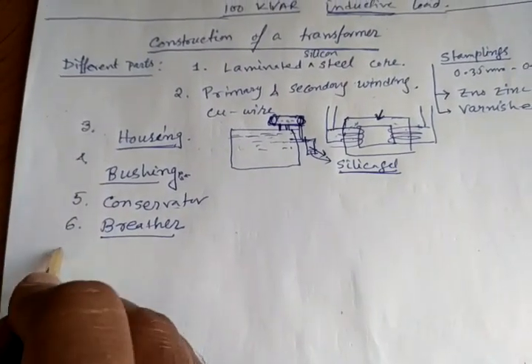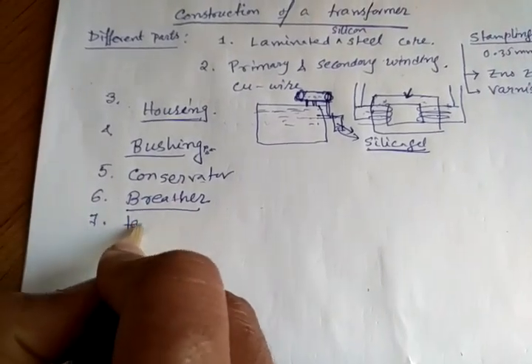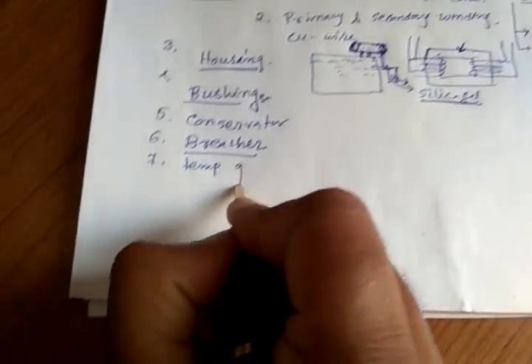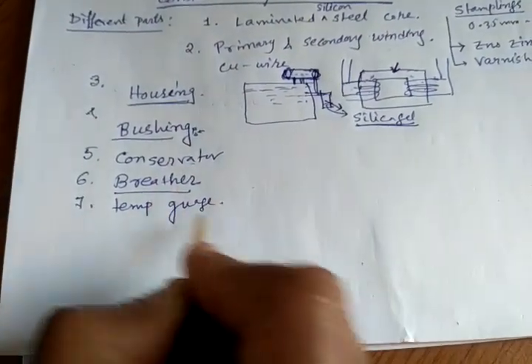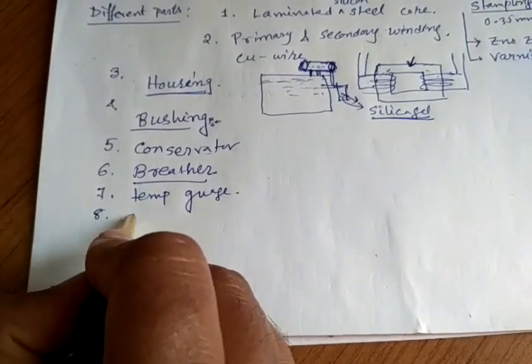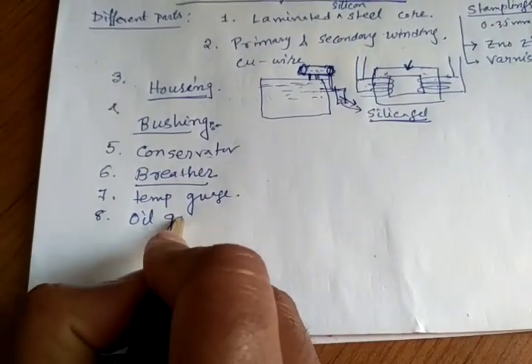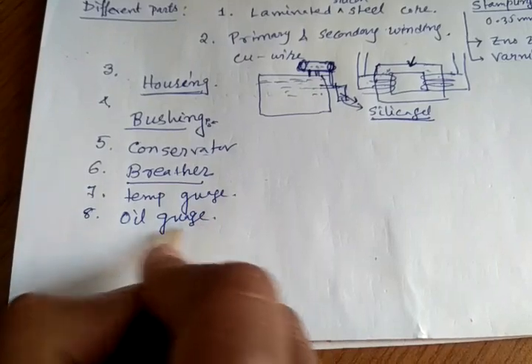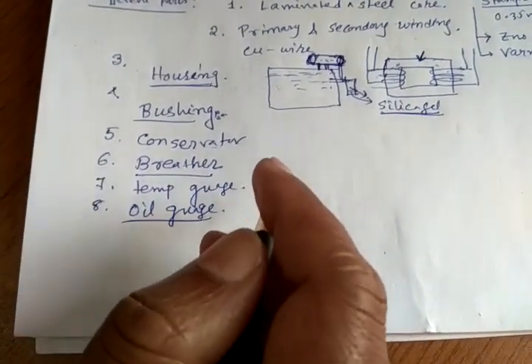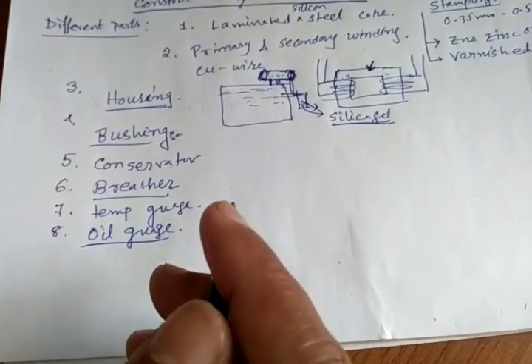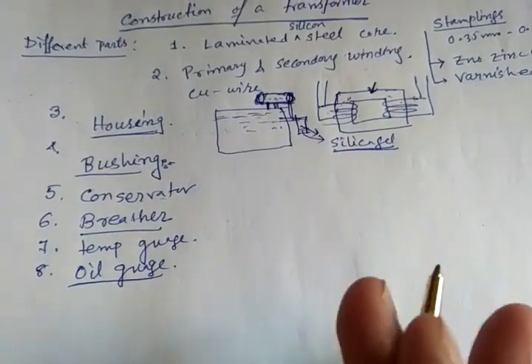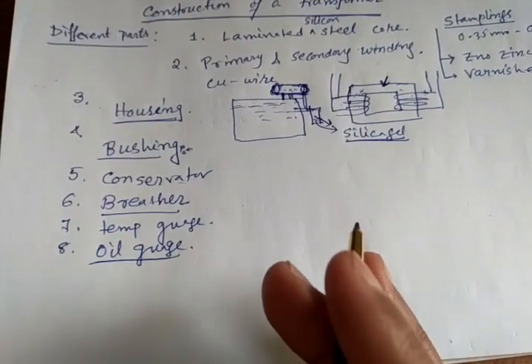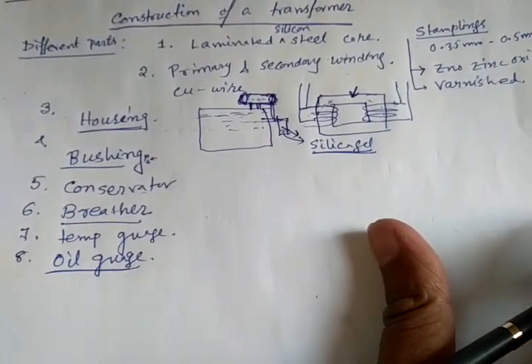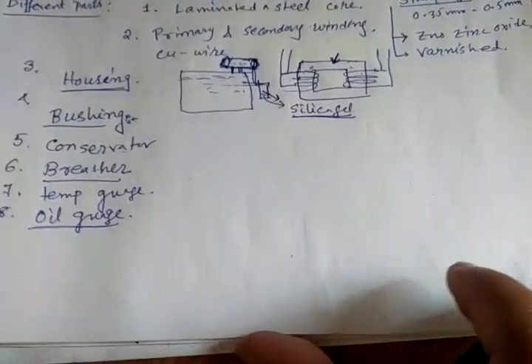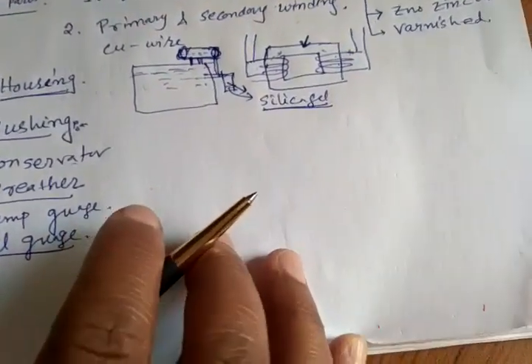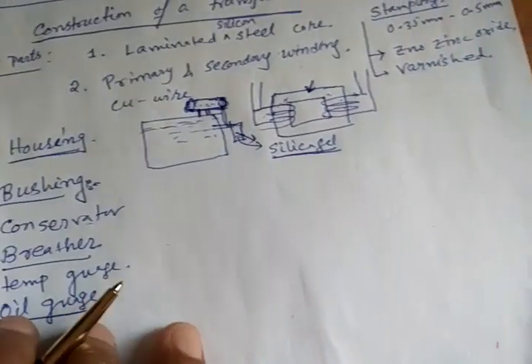And other than that, some measuring devices like a temperature gauge to measure the temperature rise of the transformer, and some oil gauge. This oil gauge is used to measure the oil level. So if it is below the threshold level, then we need to put in some more oil, or we may have to remove the transformer from the circuit.